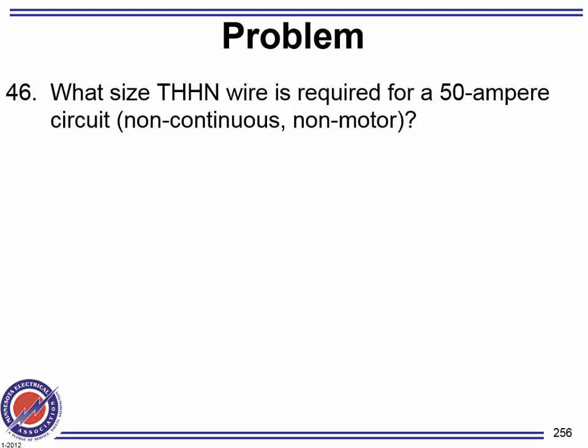What size THHN is required for a 50 amp circuit, non-continuous, non-motor? 50 amp, non-continuous, non-motors. What do you go by? It's a THHN, so if I was derating, I can go all the way to 90 degrees. I'm not derating, so you go strictly by the amps of the equipment.